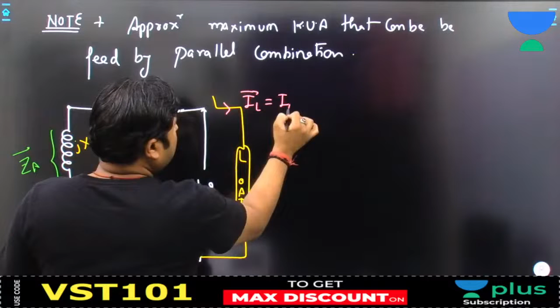Now please observe here, you can assume the EMFs as EA and EB. If EA and EB are equal, you can assume it like a single source, and that single source is delivering current which has two paths: one having impedance ZA and one having impedance ZB. We all know current always tries to flow through the low impedance path, so maximum current will take that path with lower impedance, and that side of the transformer will get overloaded first.